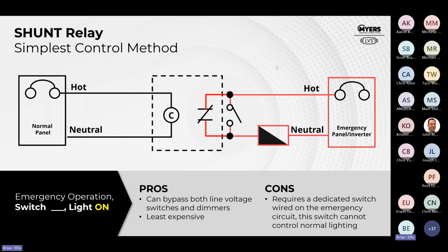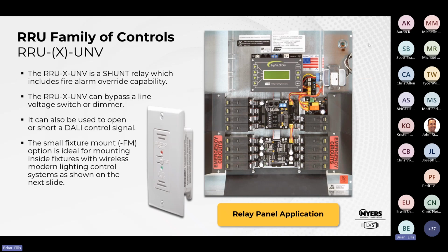Where do we use this? We'll use this if we have a relay panel. Let's say you have a relay panel and you're bringing a normal circuit out to your devices, and an emergency circuit out to your devices. If you do not have a UL924 listed relay panel from any one of the manufacturers that you represent, you can provide an RRU in line with the emergency relay, and that will shunt the control upon loss of normal power.